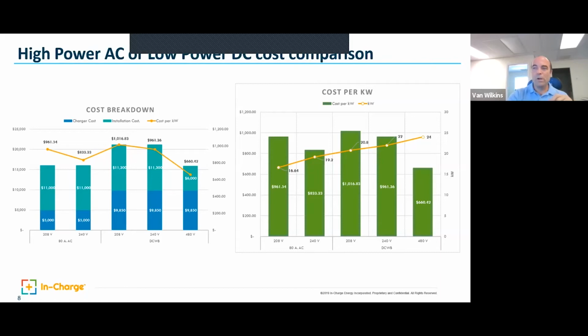But where you really get the payoff is where I have a max 80 amp charging on the AC, I can do 24 kW on the DC. And to give you an idea of the nuance, a lot of times you'll hear manufacturers say, hey, we sell a 19.2 kW charger or a 7.2 kW charger. They list it based on its highest possible voltage, which is residential voltage, 240 volt. Commercial buildings are 208 volt. So that 7.2 kW charger, on almost all commercial buildings, will only be 6.6 kW. That 19.2 kW AC charger really is only a 16.6 kW charger on a commercial building, because the voltage is lower — it's 208 volt, three phase, lower voltage.